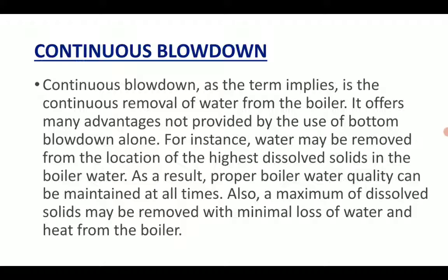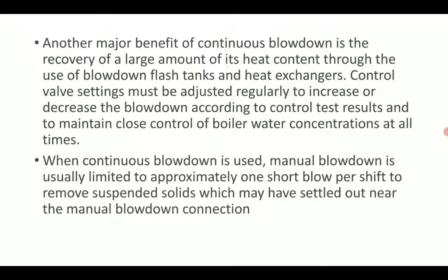So it is continuously removing the bottom side of the boiler water. Like this you can reduce the sludge, reduce the scaling formation in the bottom of the boiler, and also improve the efficiency of the boiler. Another major benefit of continuous blowdown is the recovery of a large amount of its heat content through the use of a blowdown flash tank and heat exchanger.